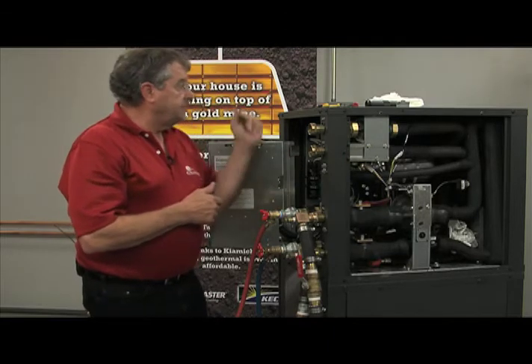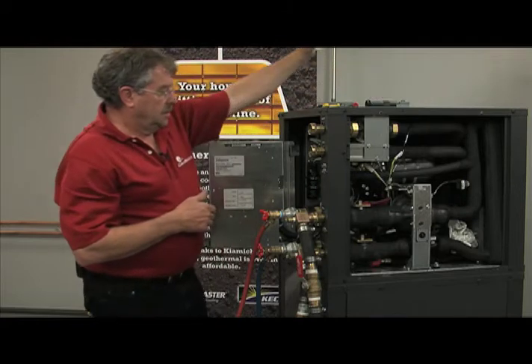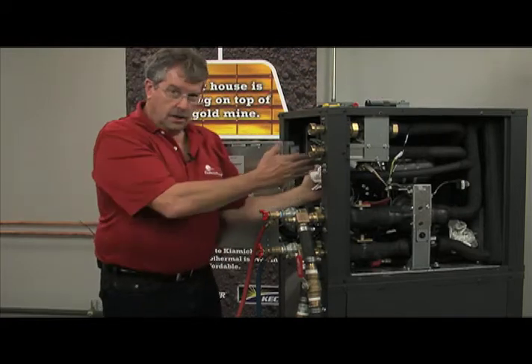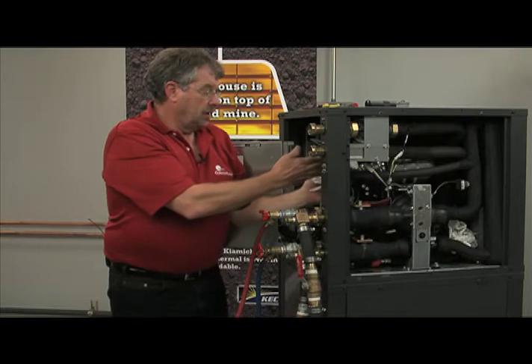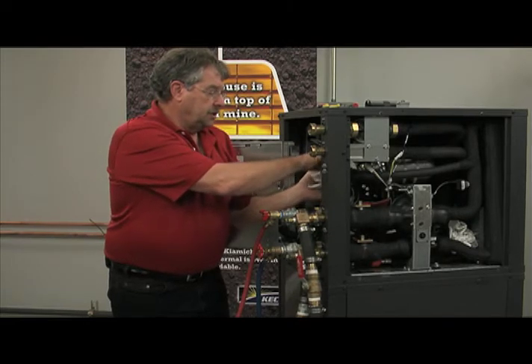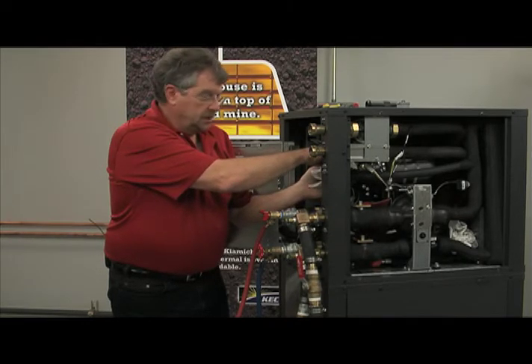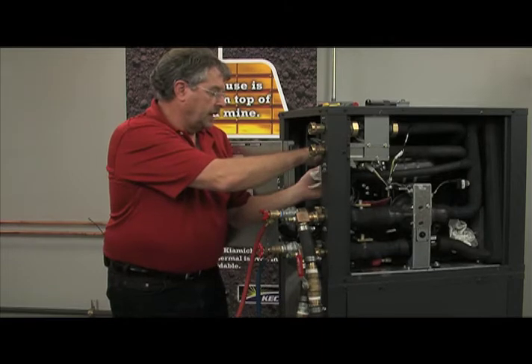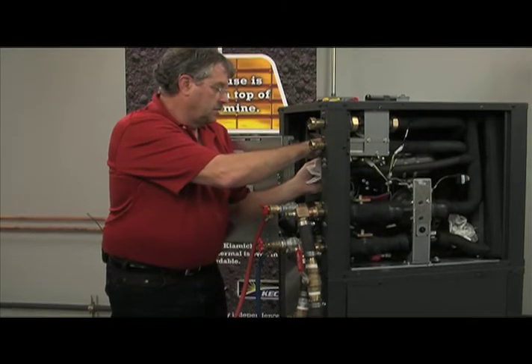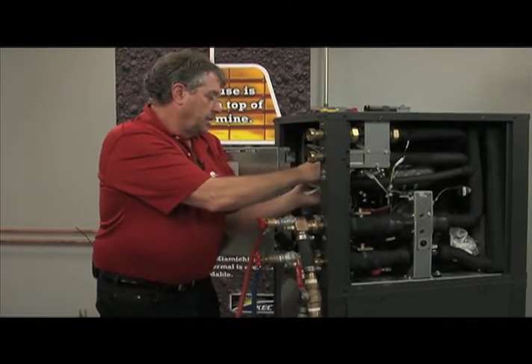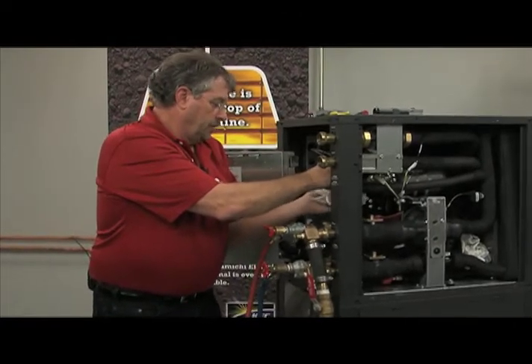But one of the steps we need to take here, we need to again pressurize our expansion tank, but we also need to burp that pipe coming in. So I'm going to remove that Schrader cap, utilize the rag here. I'm going to make sure that we have fluid right to that point, which we do.